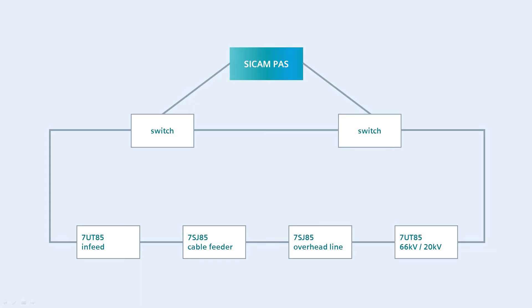In our example, all devices should communicate via IEC61850 protocol in a ring structure using RSTP, as we see it here on this graphic. As a substation automation system, we use a SICAM PAS, which we integrate in the communications network via two switches.